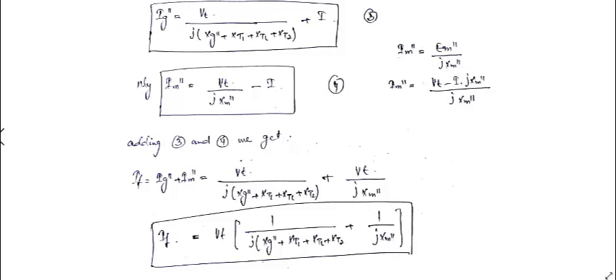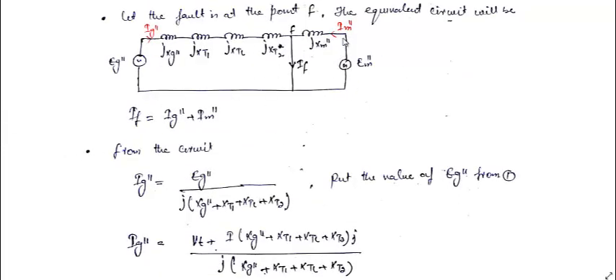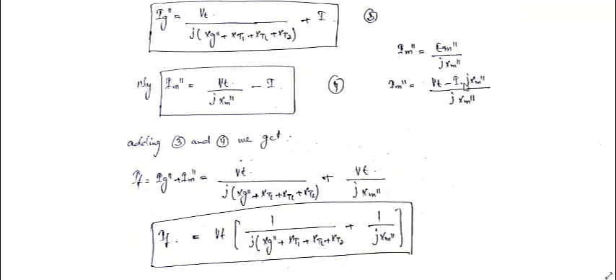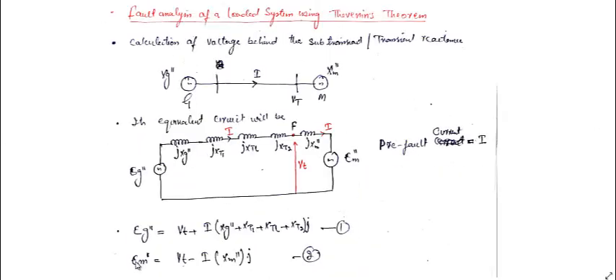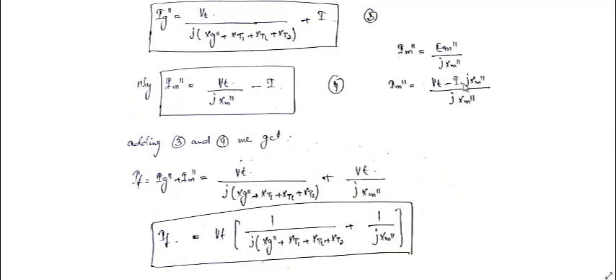During the fault, Im double dash = Em double dash divided by jXm double dash. Substituting equation 2 — replacing Em double dash with Vt minus I times jXm double dash — it simplifies to Vt divided by jXm double dash minus I. So from these two equations we can calculate the values of Ig double dash and Im double dash.